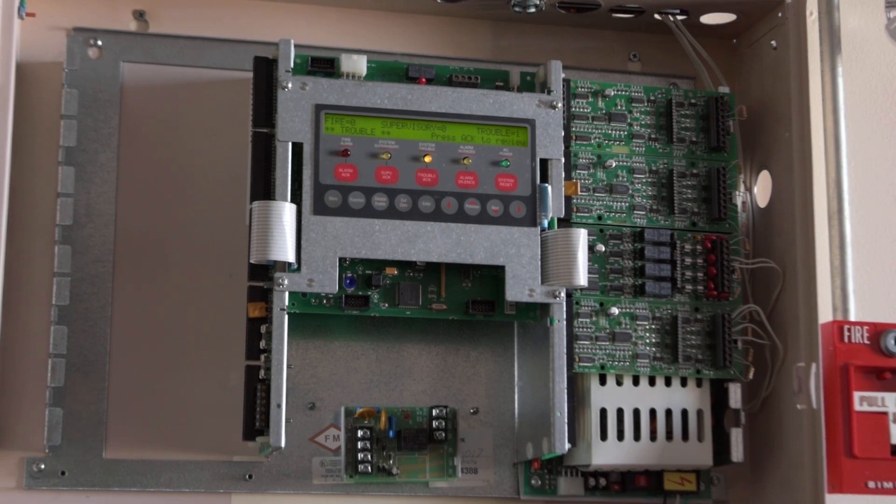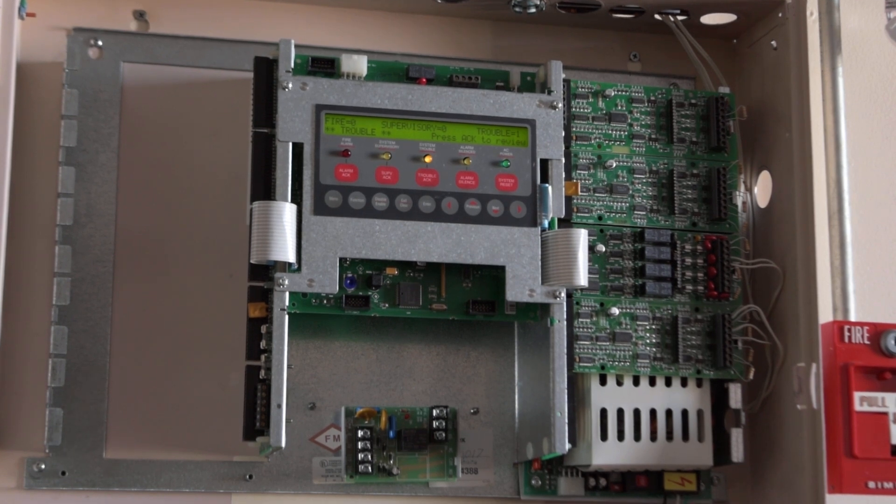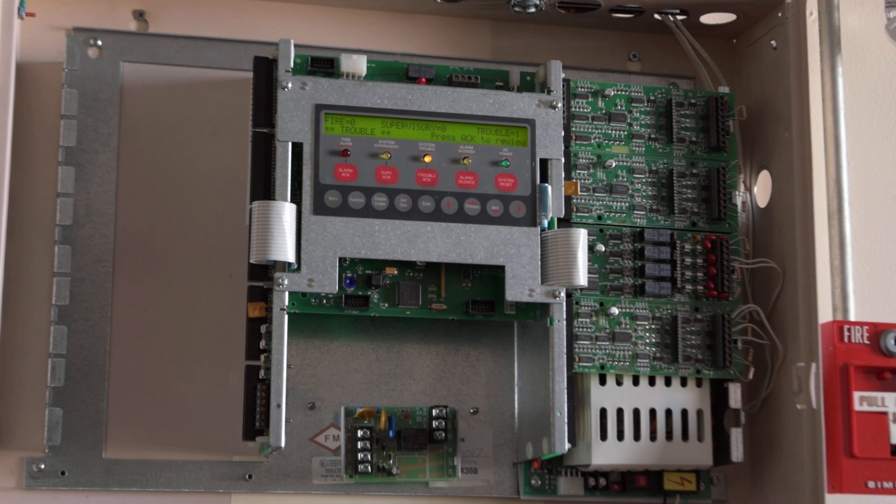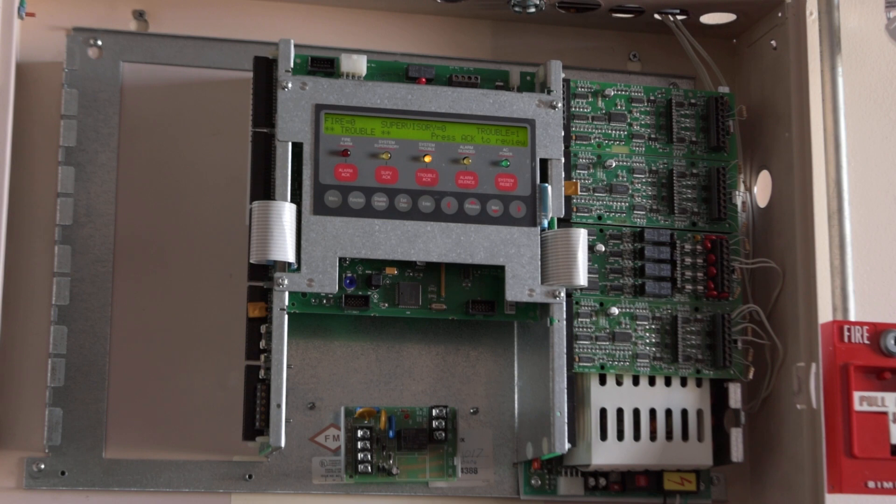Okay, there we can see the inside. We have three zone cards, so we have a total of 16 zones. There's two zone cards in the first and second slots. The third slot has a relay or NAC card, so I have it set up to have two NACs and two relays. And then that last card on the bottom is an additional zone card.